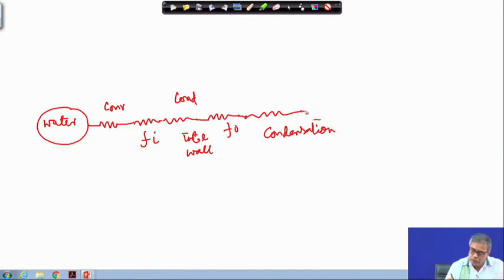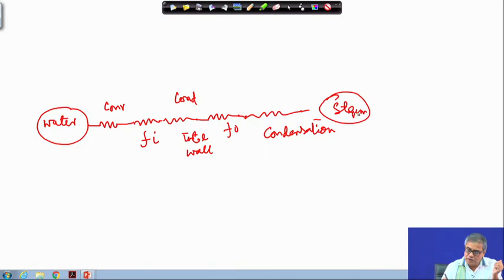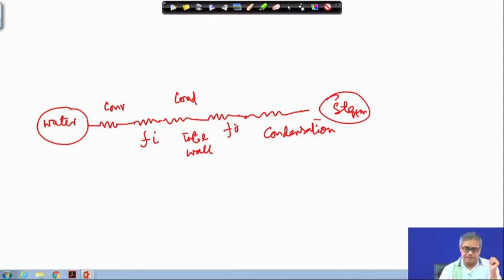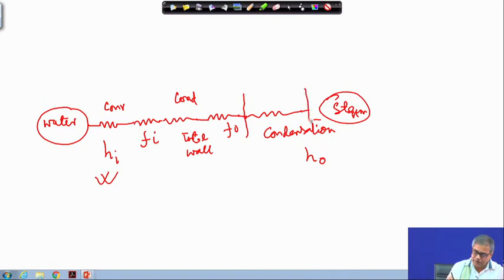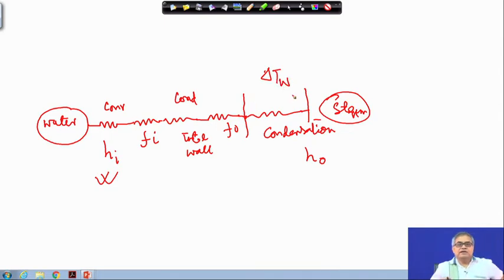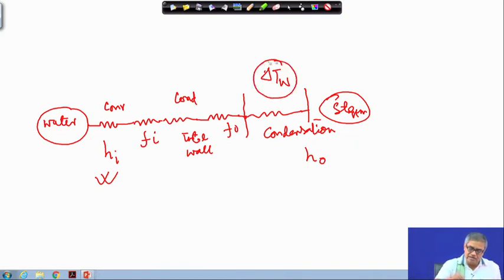This is the well-known thermal circuit, with water on one side and steam on the other. From water to steam there are five resistances: 1, 2, 3, 4, 5. The convective resistance H_i has already been described. For H_o, the temperature difference delta T_w — the wall temperature difference — is needed. Going back to the Nusselt correlation, this temperature is required.